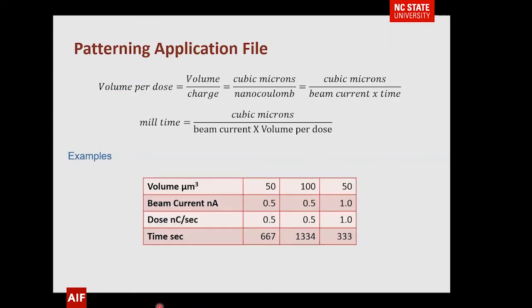Here's a typical volume per dose calculation for a patterning application file. Basically, you would do a rectangular removal using whatever beam you have, run it for a while, then use AFM or some other technique to determine exactly what volume you removed, and come up with volume per dose. As an example: removing a 50 micrometer cube volume with a 0.5 nanoamp beam is going to take about 667 seconds. If you double that volume, it's going to basically double that time.